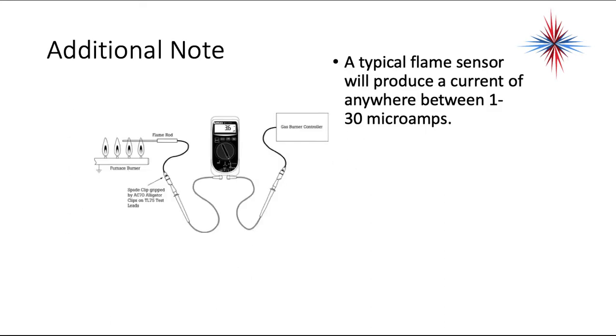A typical flame sensor will produce a current of anywhere between 1 and 30 microamps. The way to test this is you put your amp meter in series with the flame rod to the burner control. And you should get a decent amperage in there, okay? Someplace between 1 and 30 microamps. Make sure your meter's set for amps, better yet microamps, and make sure you plug your leads into the correct spots on the meter to put your meter in series for an amperage measurement.